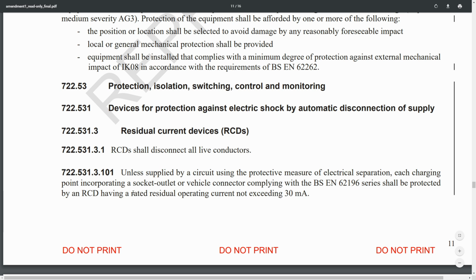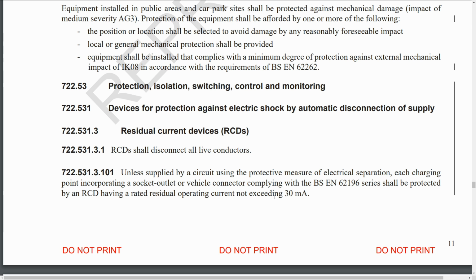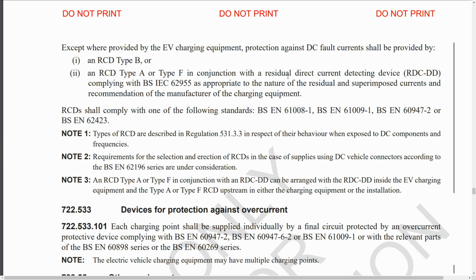Each charging point incorporating a socket outlet or vehicle connector complying with that series shall be protected by an RCD having a rated residual operating current not exceeding 30 milliamps. That's pretty much what it said before, but again it's just been rewritten a bit and it now has a new number. This part here is essentially the same, again with a new number. The main difference here is that we've now got type F added in here, so the type B was already there, the type A was there, so now we've got OR type F in conjunction with the residual direct current detecting device and the relevant standards and so on.